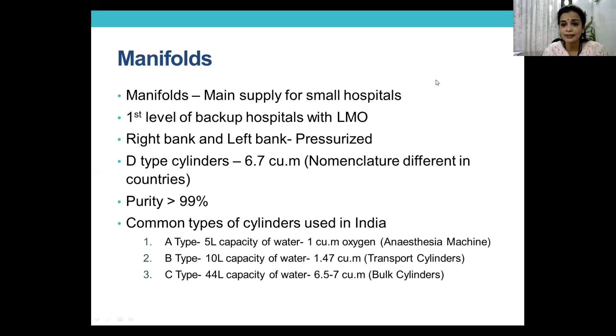And this is connected to your anesthesia machines, the very small ones that are connected to your Boyle's machine. Then you have your B-type cylinders, which is used for transporting patients. This is the small cylinders that we have in our wards. That's 10-liter capacity of water that has about 1.47 cubic meter. Those are used for transporting. Then you have your C-type cylinders, which is 44-liter capacity. I'm sorry, this is a D-type. And these are the bulk cylinders that we use in our manifold.